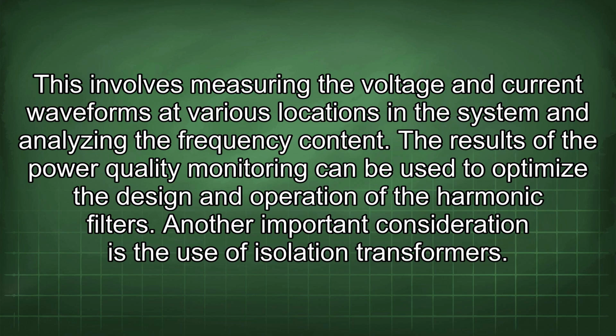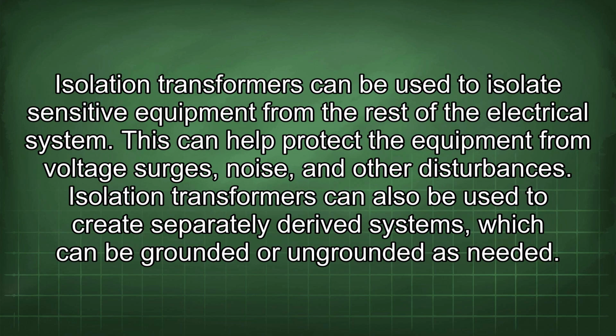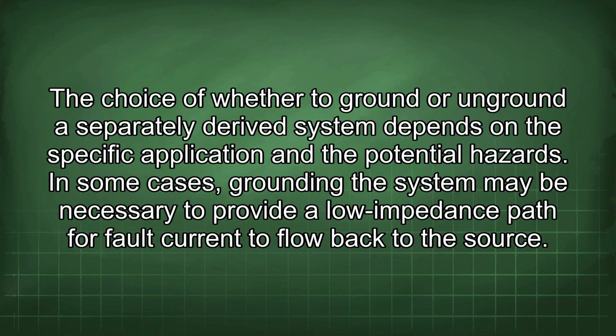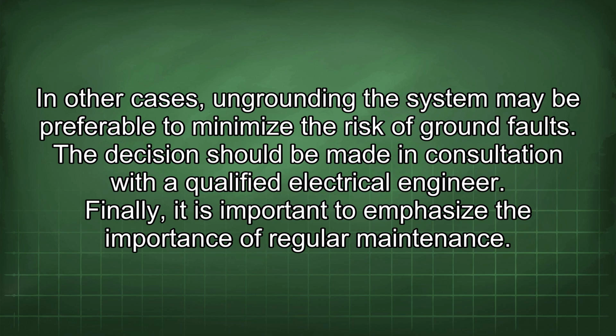Another important consideration is the use of isolation transformers. Isolation transformers can be used to isolate sensitive equipment from the rest of the electrical system. This can help protect the equipment from voltage surges, noise, and other disturbances. Isolation transformers can also be used to create separately derived systems which can be grounded or ungrounded as needed. The choice of whether to ground or unground a separately derived system depends on the specific application and the potential hazards. In some cases, grounding the system may be necessary to provide a low impedance path for fault current to flow back to the source. In other cases, ungrounding the system may be preferable to minimize the risk of ground faults. The decision should be made in consultation with a qualified electrical engineer.